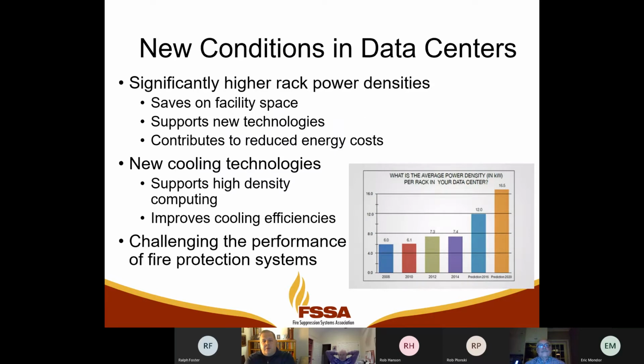One of the reasons we have some new requirements for how we protect data centers is because the IT equipment that we're putting in them has changed significantly. A major thing is that there are higher rack power densities. So, racks are the big cabinets that we put the different server equipment in, and those pieces of equipment, as they are doing faster and faster computing and handling more data, they consume more power, and power equates to more requirements to cool that equipment.